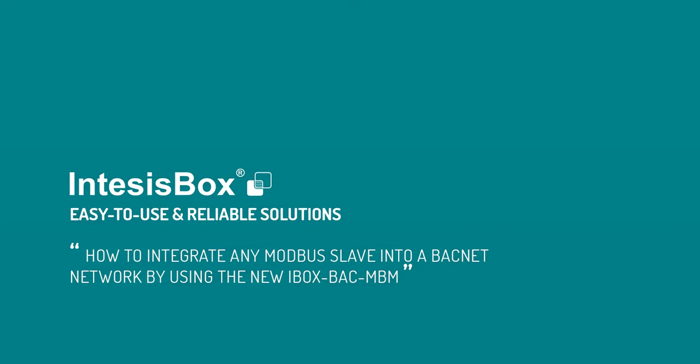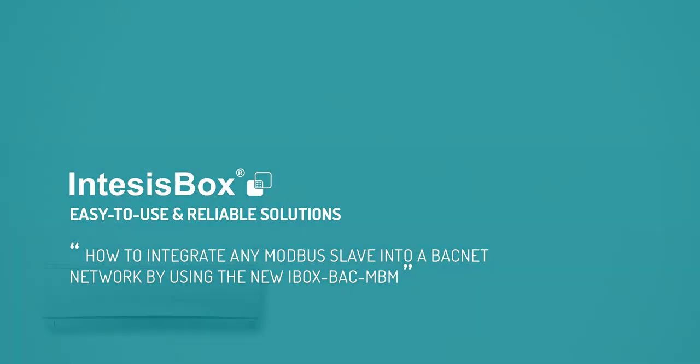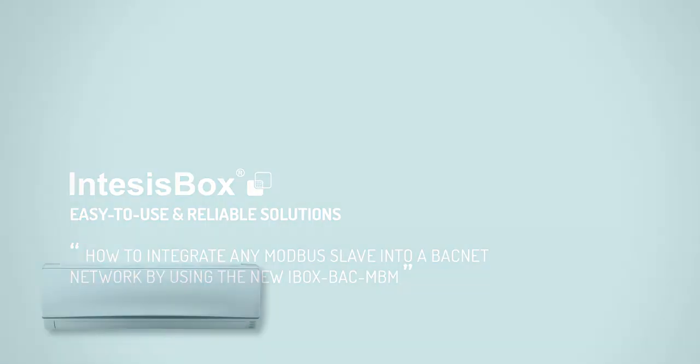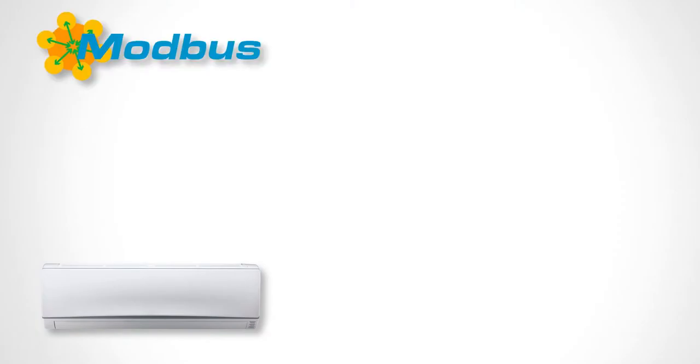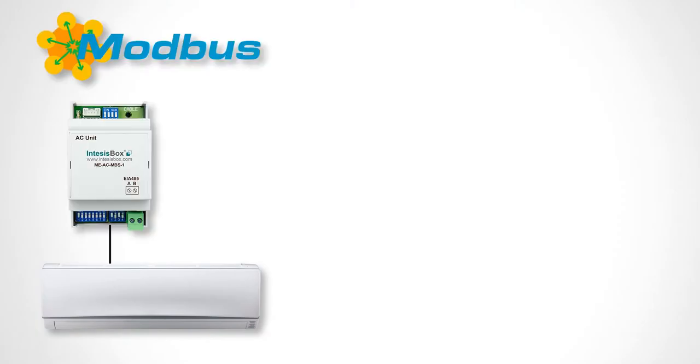In this tutorial we will show you how to integrate a Modbus RTU device into a BACnet network. To perform this integration we are going to use the new IntesisBox iBox-BAC-MBM gateway. As an example we will have an air conditioning unit connected to Modbus by using the MEAC MBS1 gateway and we will integrate the next registers into BACnet.